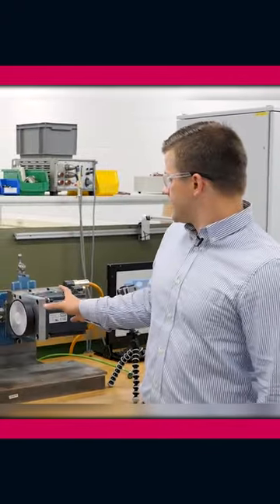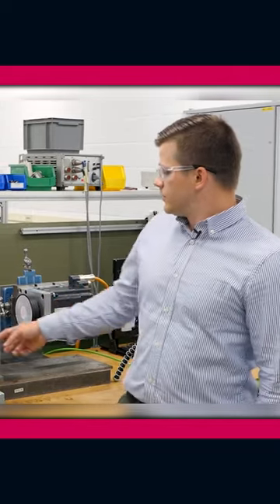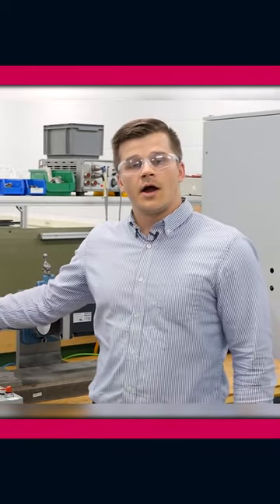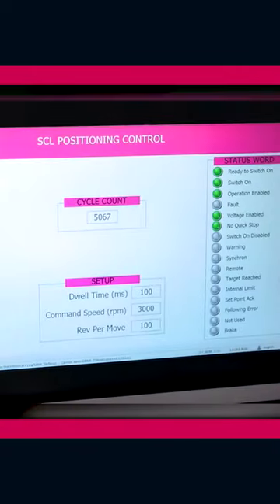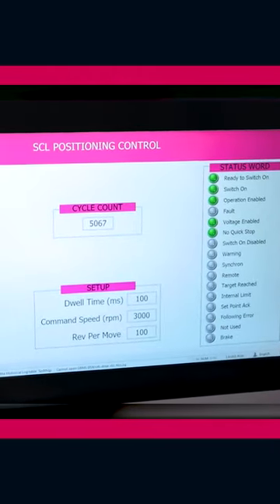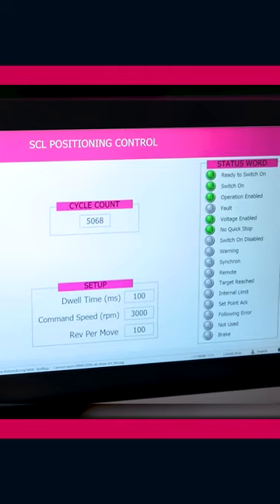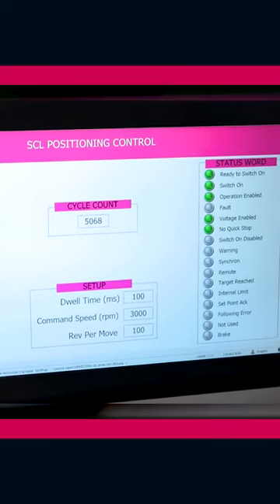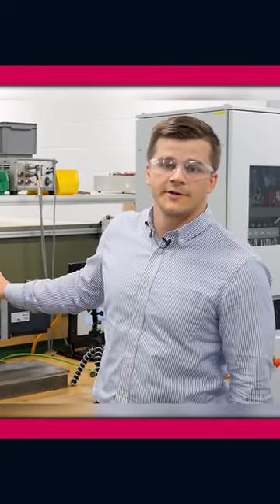We've let the motor run for an extended time. You can see on the HMI it's over 5,000 cycles and even though the encoder cable is disconnected, it's still consistently hitting the 12 o'clock on its position stopping time.